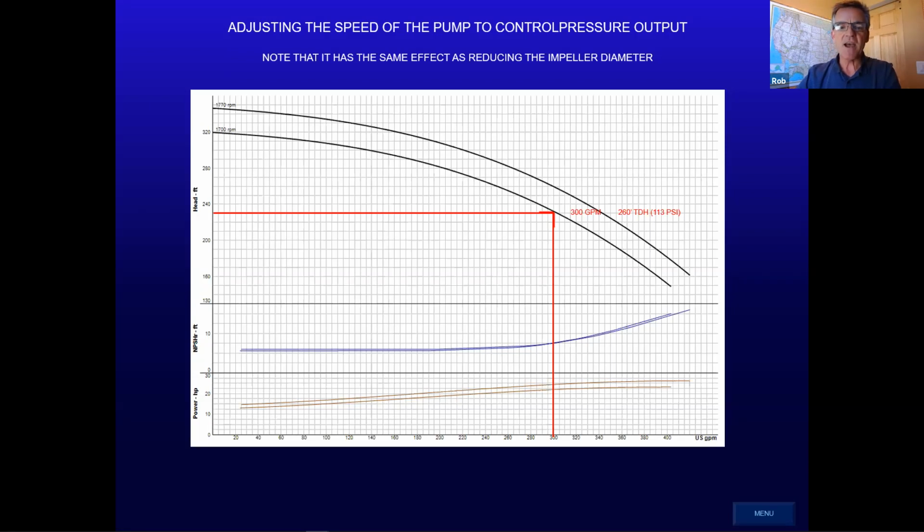The other thing that a VFD does is it keeps your mainline pressurized at whatever the operating pressure is all the time, even if there's no demand. On a mainline where the pressure fluctuates a lot, the fittings are moving around, there's water hammer, etc., which tends to be pretty hard on them. If you keep a mainline fully pressurized all the time, there's very little movement in the system.